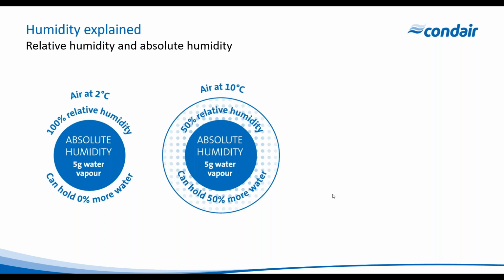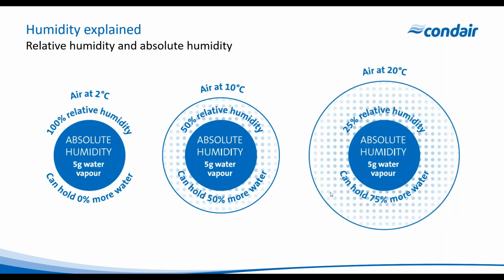So let's say we take this one step further and we increase that air temperature to 20 degrees C. Again, we haven't taken any moisture out or put any moisture into the air, but we have the same absolute level of humidity. So with that 5 grams of water now in air at 20 degrees C, we're only 25% saturated. So it can hold 75% more water. So this can have a significant effect when we're changing the temperature of air. And that's what we're doing when we're taking air from an outside environment to an inside environment.